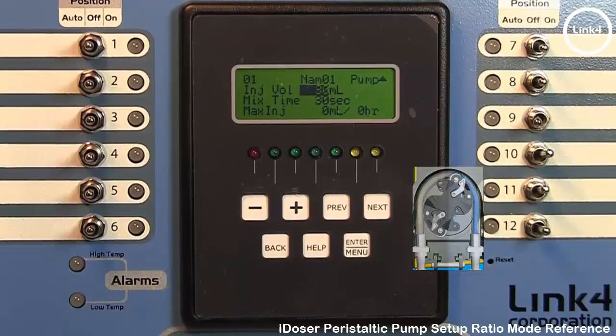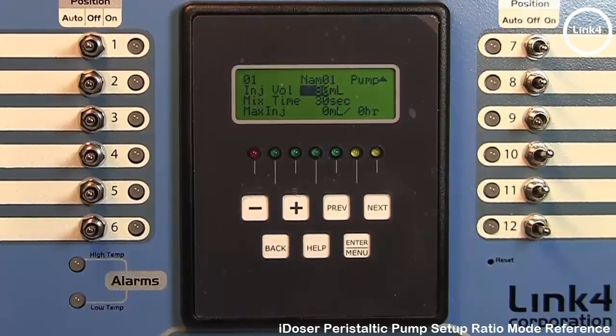Next, we have the mix time. The mix time is the time between injections to mix the nutrients or acid in the tank before starting another injection cycle. Now the max injection is the max amount of nutrient or acid that will be injected in any given period of time, which is useful if you have like sensor failure.